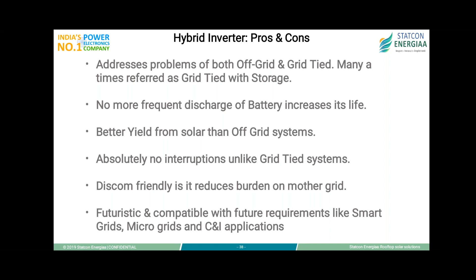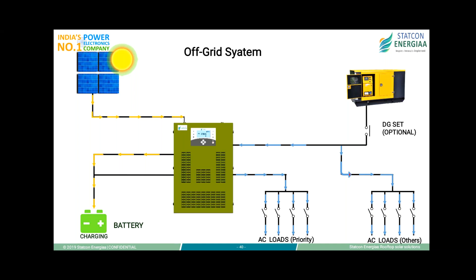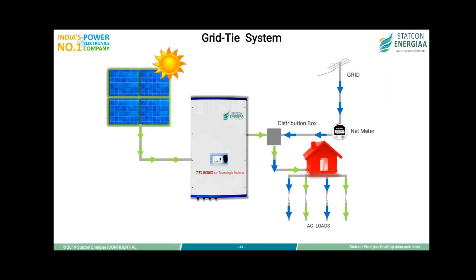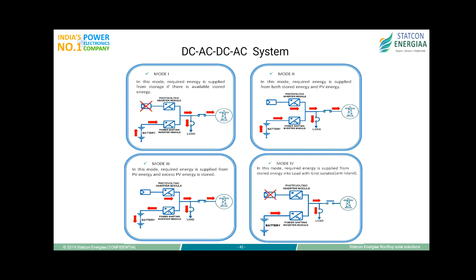Now we'll talk about some different configurations of PV with DG and storage. So this is a typical scheme with solar being installed with batteries as well as DG set, and this is a backup application. This is a grid-tied system that we all know. This is a very typical scheme we call the DC-AC system, where required energy can be availed from both solar as well as the batteries. So together they can export the power into the grid.